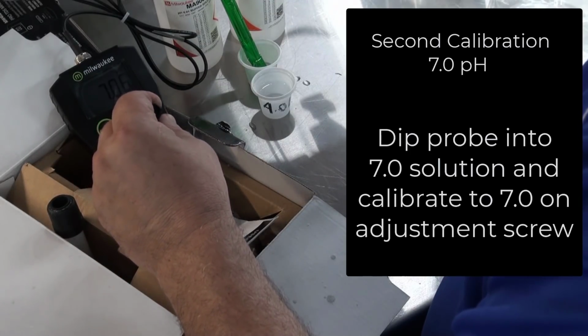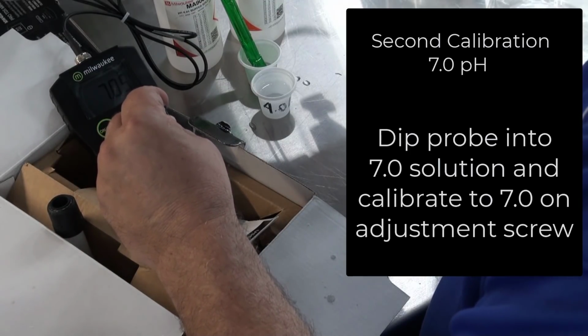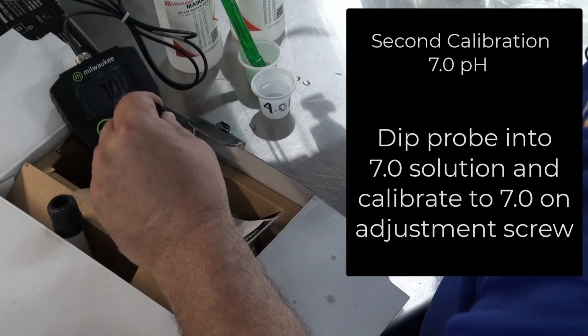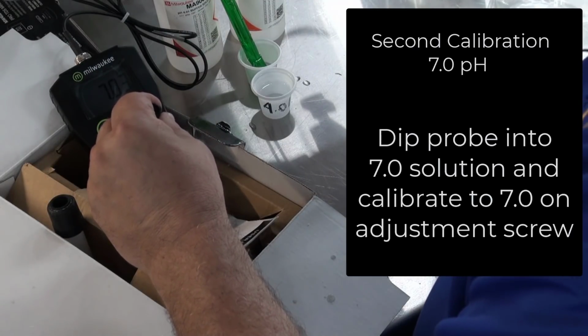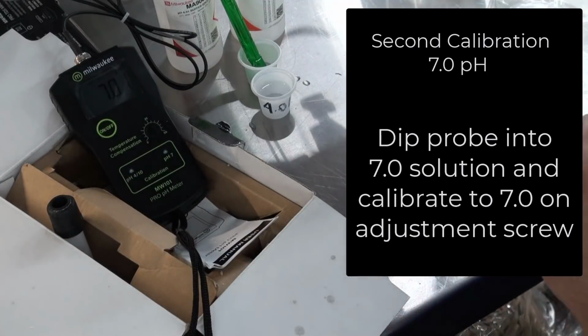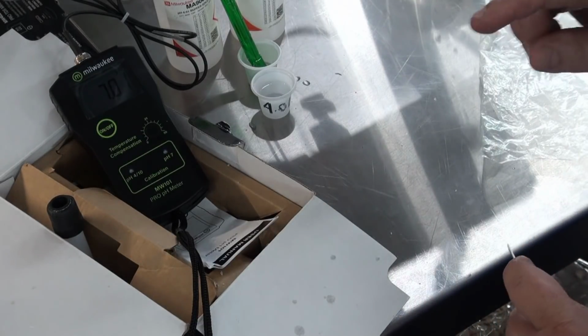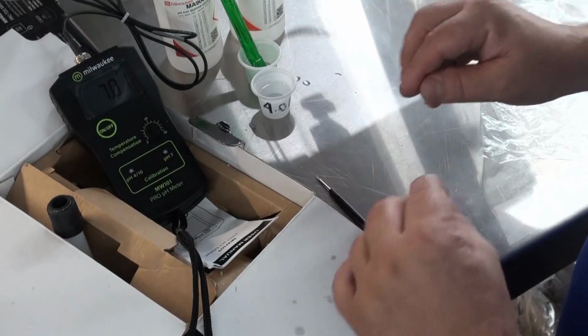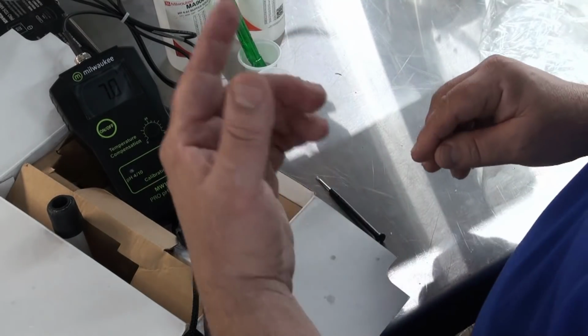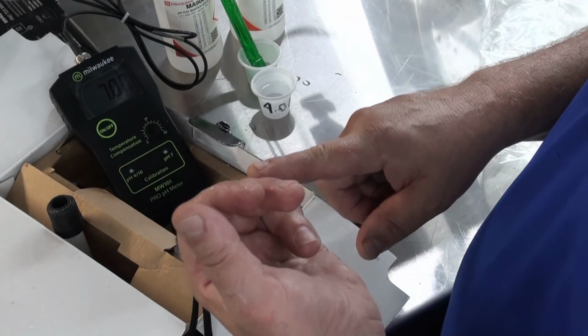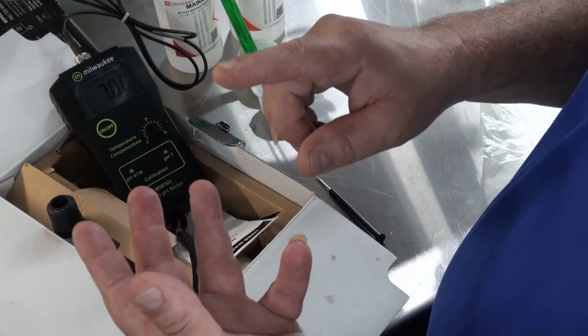We put it into the 7, and we start adjusting the 7. Now remember, you don't need to touch it much. It's slight. Okay, it's very fine. And there's your 7.01. Now, this meter is calibrated, okay? This meter will read RO water. It will read city water.